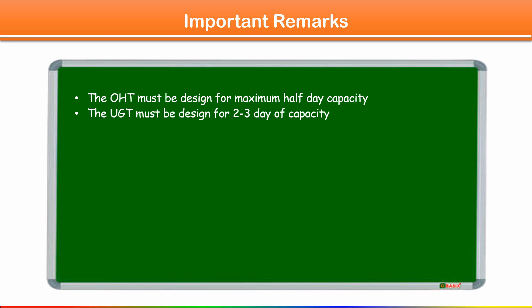Before sizing the overhead tank and underground tank, there are some important remarks to remember. As per standard, the overhead tank (OHT) must be designed for maximum half day capacity. The underground tank (UGT) must be designed for two to three days of capacity.